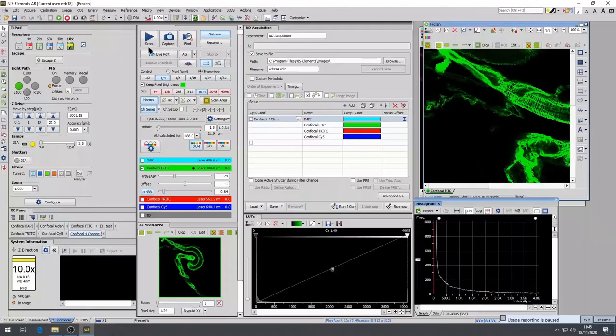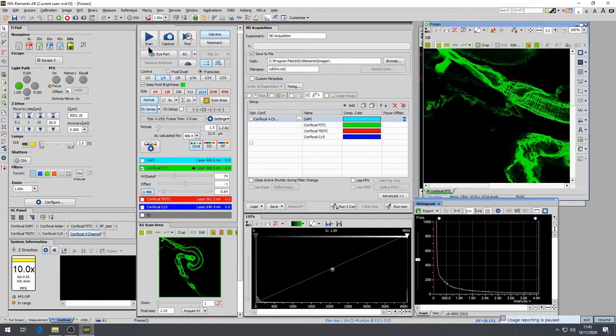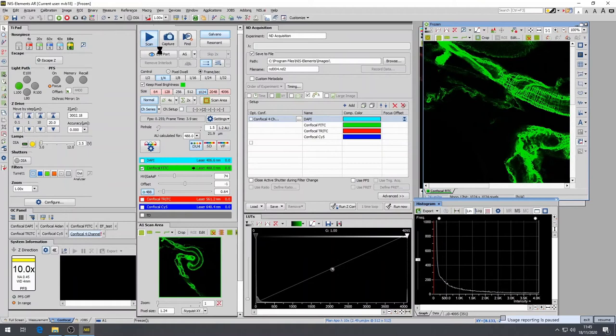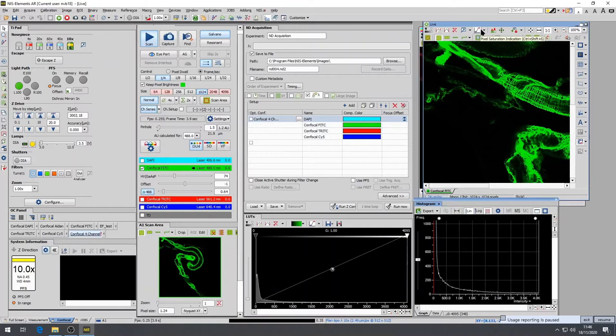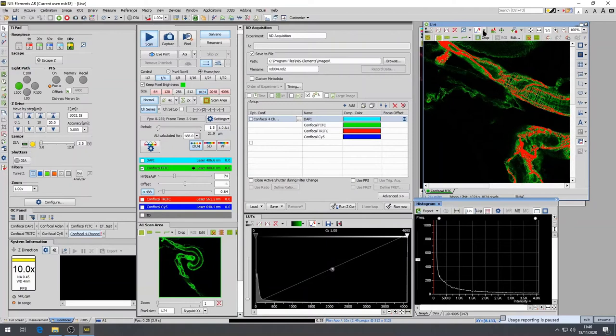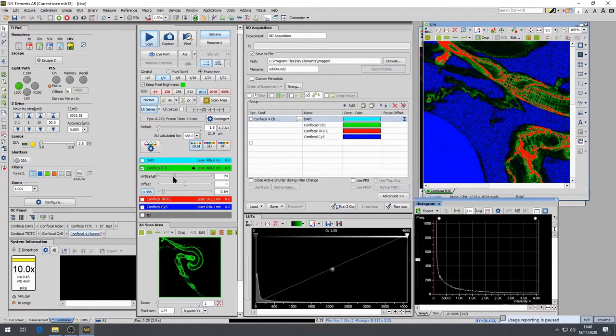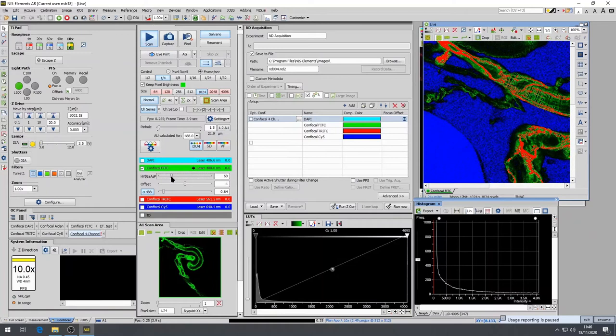When you are setting up the laser power and PMT gain for each individual channel, it is beneficial to identify whether you are over or underexposing your sample. For this, you can apply oversaturation colors to the live image using a drop down menu in the LUT window at the top right of the screen. Clicking on the arrow allows you to choose the color for oversaturating pixels and for undersaturated pixels. Using this, you can change the laser power and the PMT gain to reduce the number of oversaturated pixels to a minimum and decrease the background so undersaturated pixels can be seen.